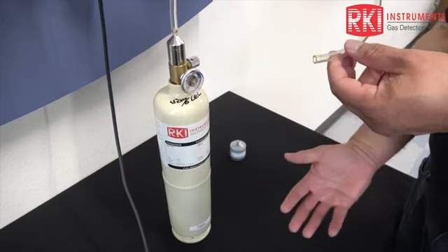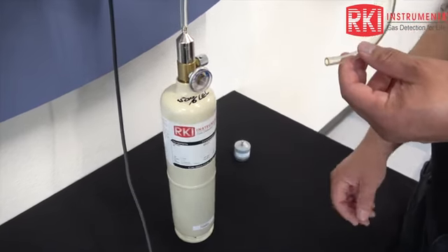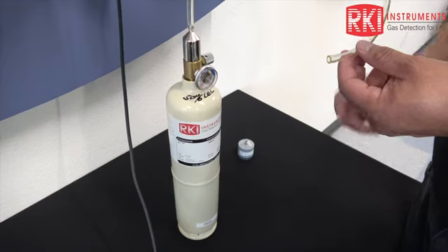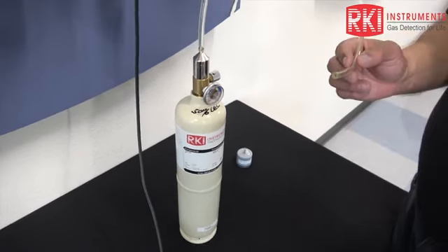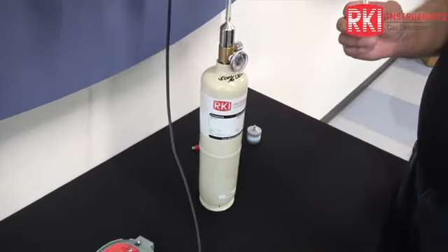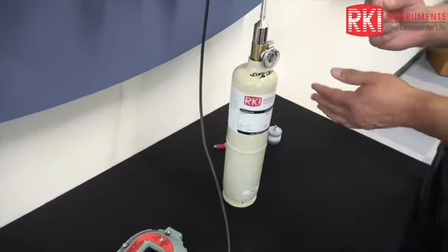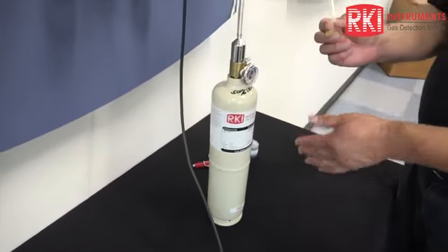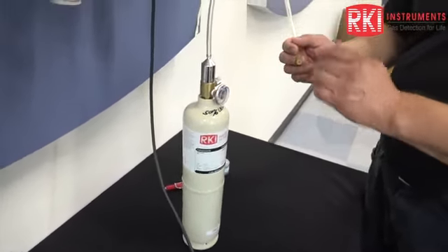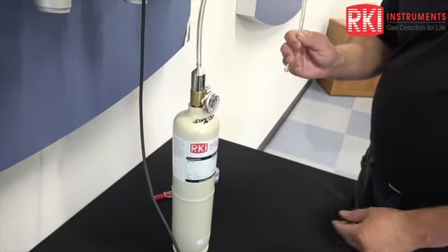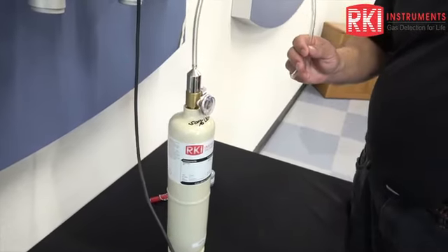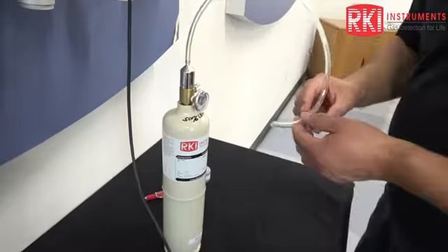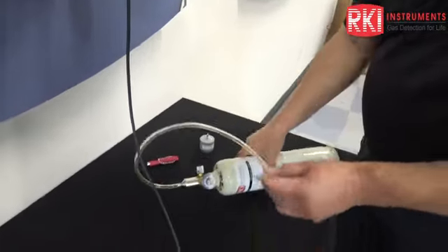But when you get down into really low ppm levels and you have a very sensitive sensor, then there will be differences between a detection that the sensor picks up from ambient air, which has humidity, versus what the sensor will detect and read out picking up dry air from a cylinder. So we want to humidify that sample when we're working with a very sensitive ppm range sensor. Okay, so just a little bit of discussion about that.